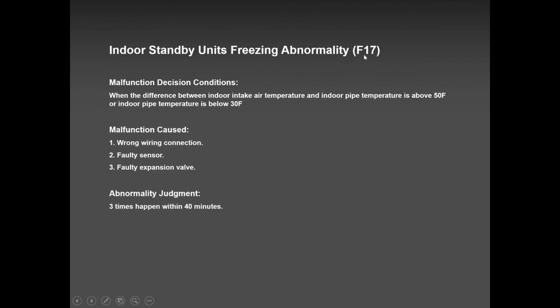So that's your F11. F17 is the error code where the guy crossed the wires. Now the guy will call me and say, Paul, it ran the whole winter. I never have issues. I said, yes, it will run the whole winter, no problems, because F17 is freezing of indoor unit coil. So in heat mode, the indoor unit will never freeze, only during defrost cycle. And during defrost cycle, we don't have an F17 error. So guys, indoor unit freezing in cooling, F17, check your wire. Wrong wiring connection. That's 99.9%.